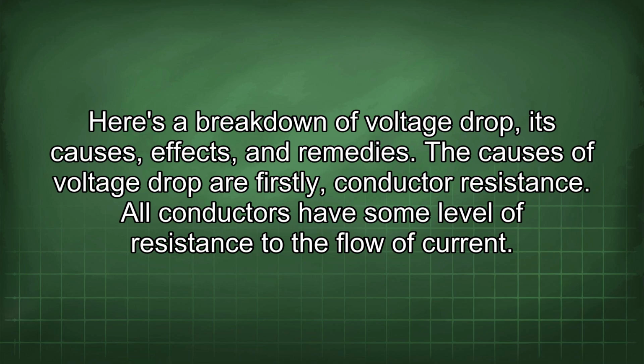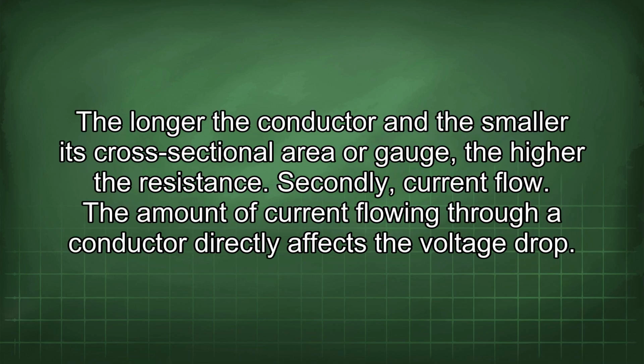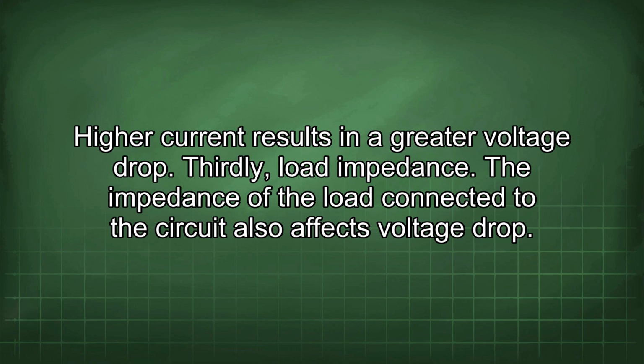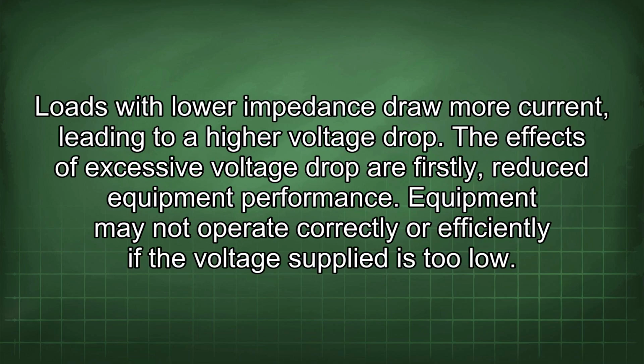The causes of voltage drop are, firstly, conductor resistance. All conductors have some level of resistance to the flow of current. The longer the conductor and the smaller its cross-sectional area or gauge, the higher the resistance. Secondly, current flow. The amount of current flowing through a conductor directly affects the voltage drop. Higher current results in a greater voltage drop. Thirdly, load impedance. The impedance of the load connected to the circuit also affects voltage drop. Loads with lower impedance draw more current, leading to a higher voltage drop.